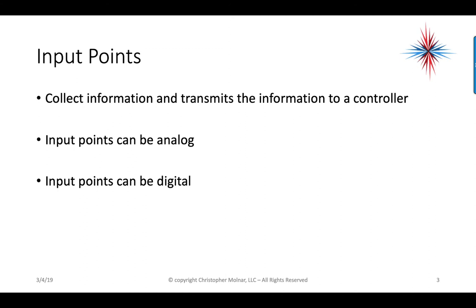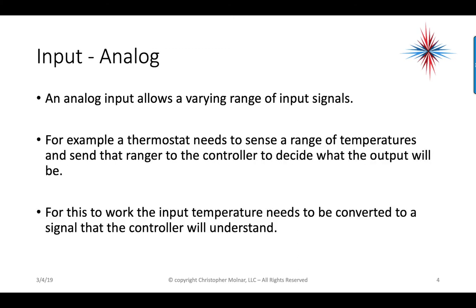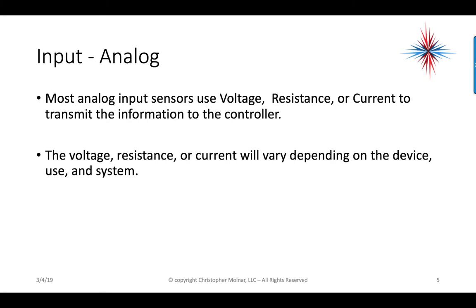The input points can be analog or digital — there's a difference between the two. Analog inputs allow a varying range of input signals. For example, a thermostat needs to sense a range of temperatures and send that range to the controller to decide what the output will be. The input temperature needs to be converted to a signal the controller will understand. Most analog input sensors use voltage, resistance, or current to transmit the information.